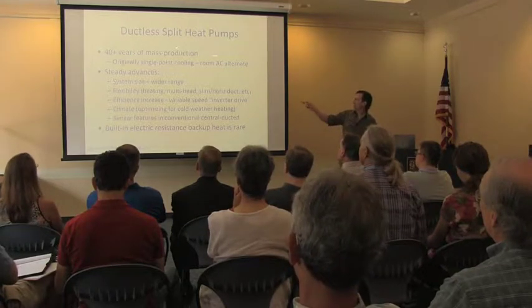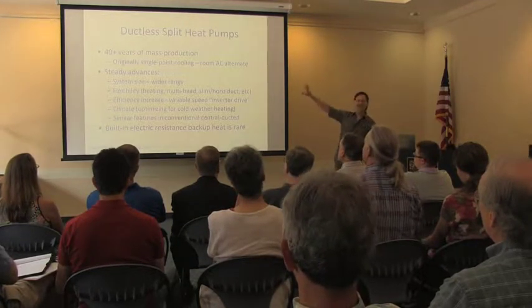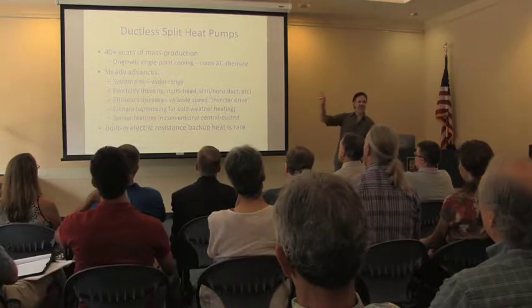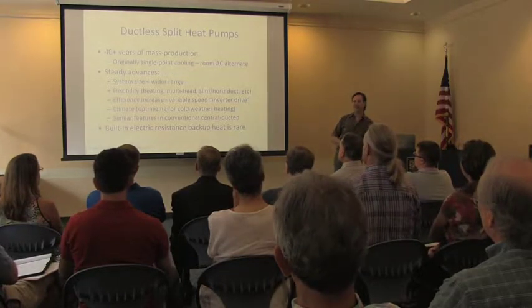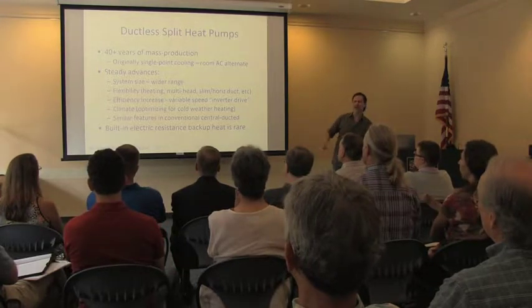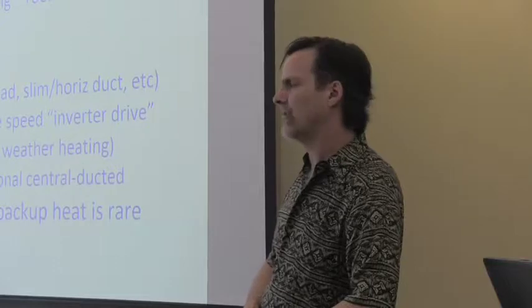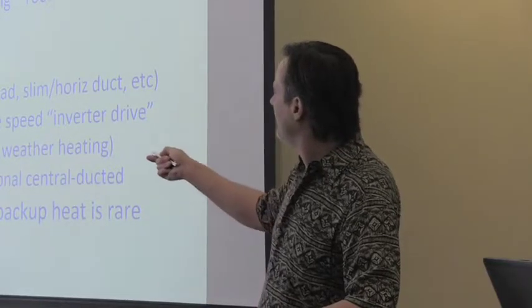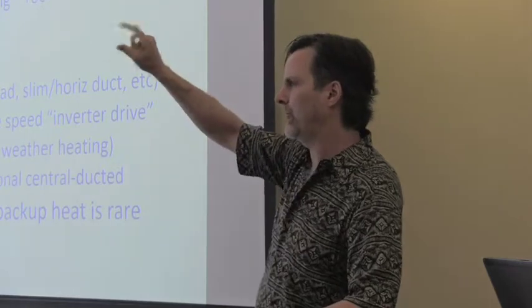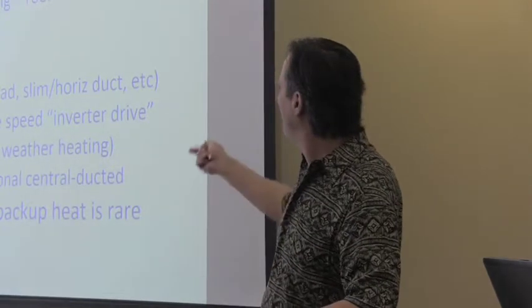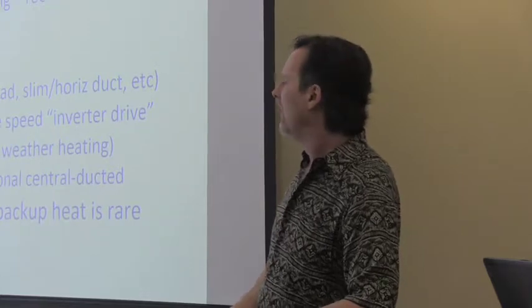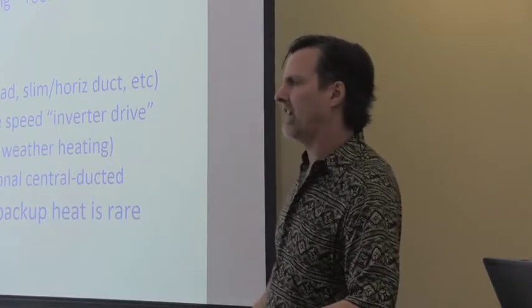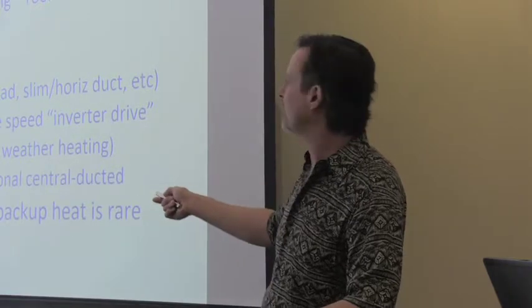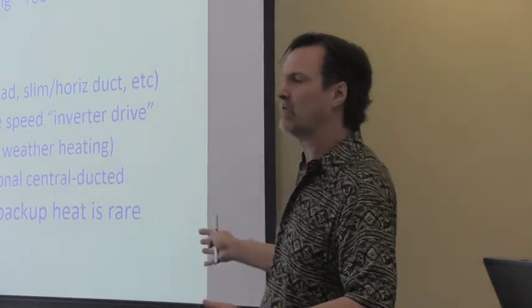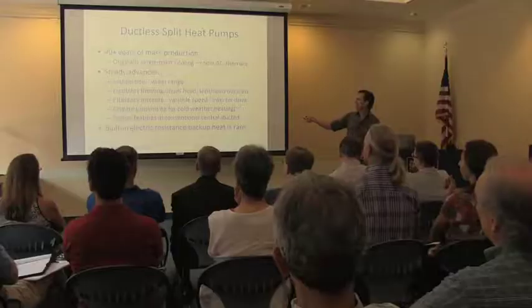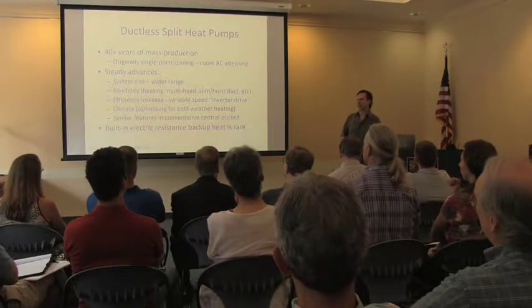Now, the ductless split heat pumps, you've seen these things, right? The little pictures that I showed you, they're in hotel lobbies and restaurants and different places all over. These things have been around for at least 40 years, originating in Japan. They started out as a single point cooling, where you'd have one indoor unit and one outdoor unit. And it was an alternative to the room air conditioner. And basically, over the last 4 or 5 decades, there have been a lot of advances. A much wider range of system size, so the amount of heating or cooling capacity. Adding heating in so that it's not just an air conditioning solution.